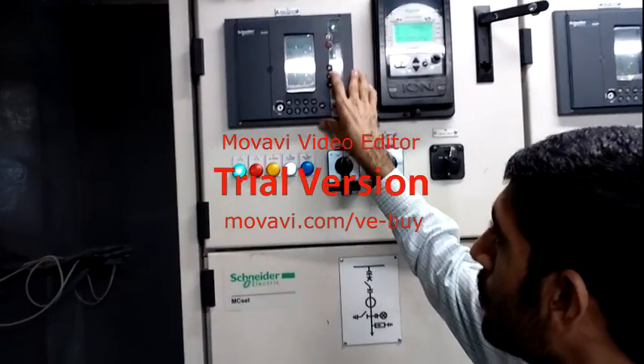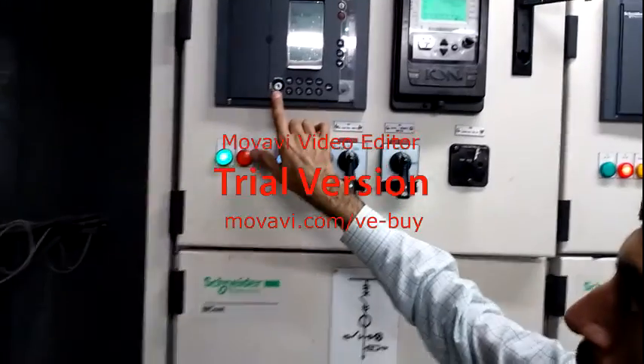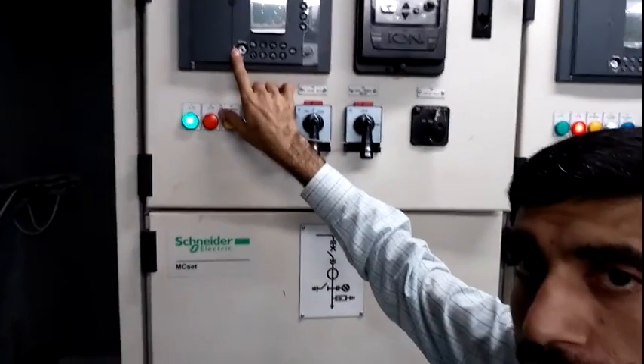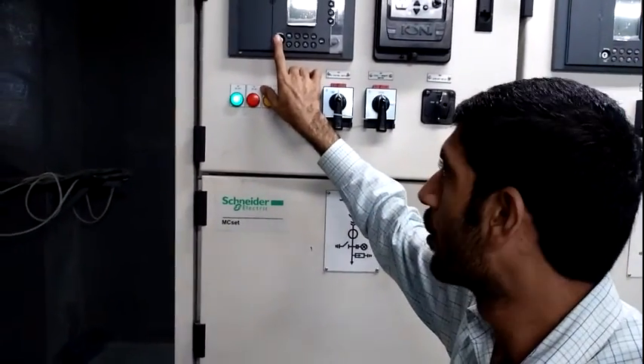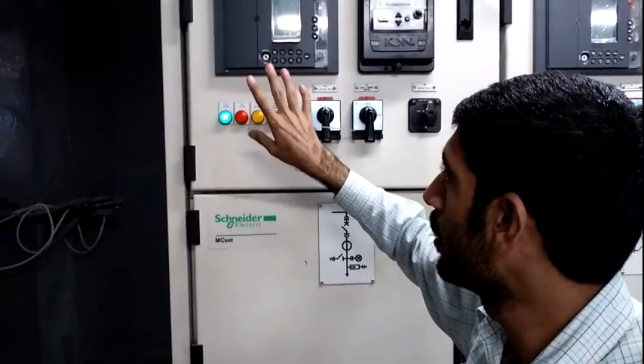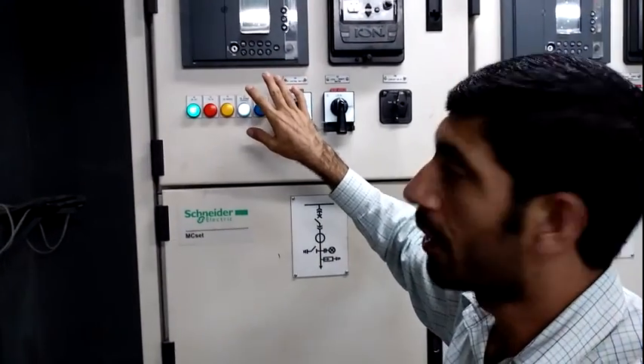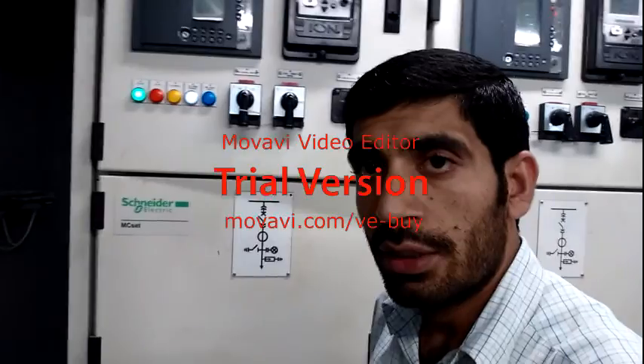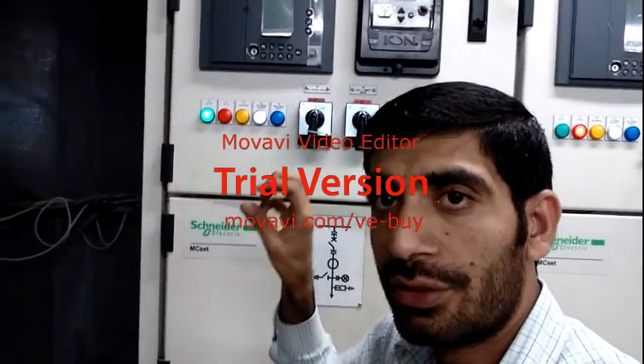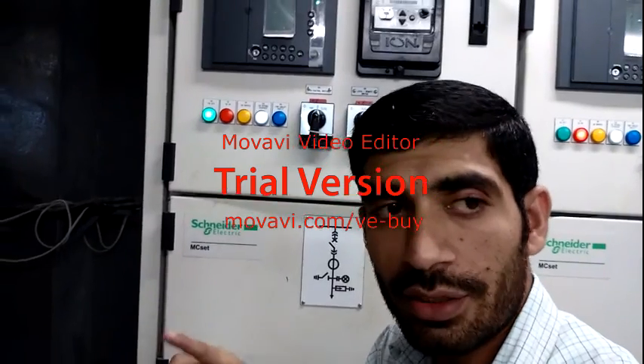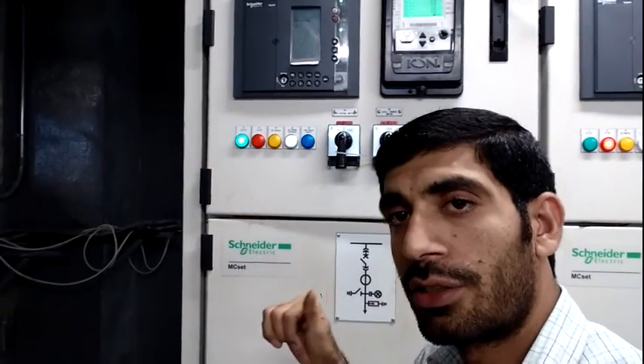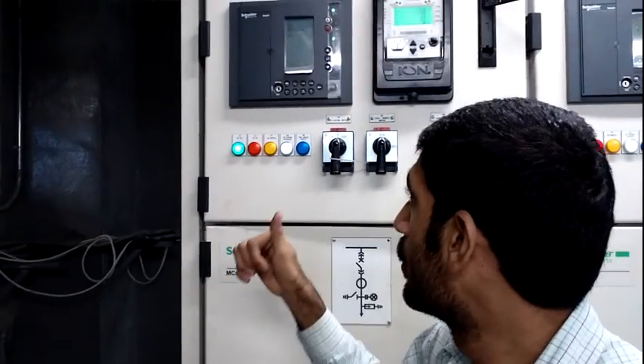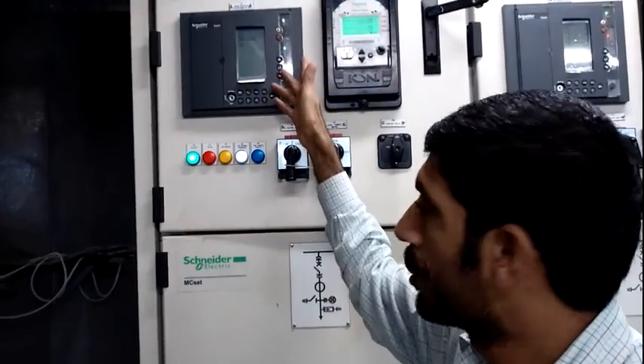All this information is saved in this relay, and it is used for local and for remote. You can control this relay in local and remote conditions. Both conditions you can use this relay. We set the rated load that we need in this relay. If the load is going to rise, this relay gives the first stage over current, and at the next stage this relay will trip and show the indication here.